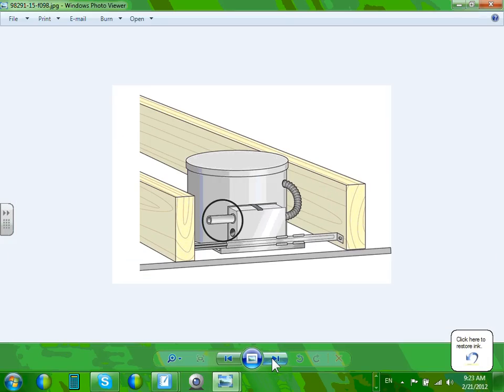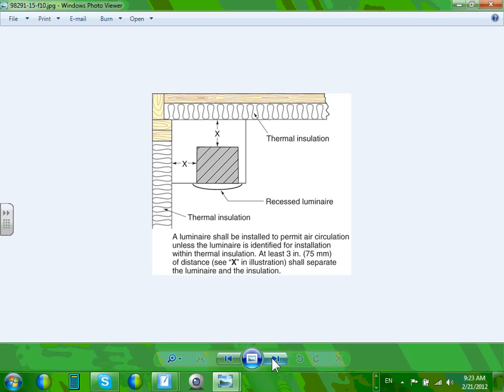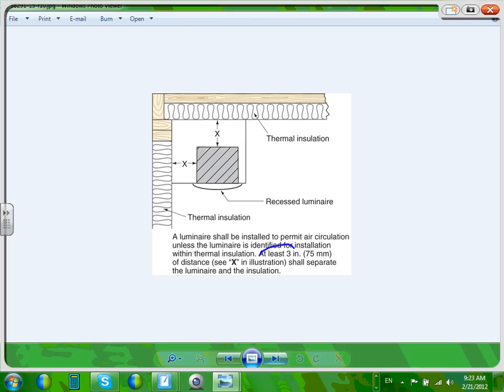When we talked about residential, guys, if your fixture is to be buried by insulation, which is not commonly used in commercial but in residential all the time, then your fixture has to be rated for what? IC, insulation contact, right? Everybody knows that from last year, IC. Otherwise, if you don't want to insulate them, then you have to separate them from thermal insulation with 3 inches, I believe. 3-inch separation, and who's going to go move the insulation? So most of these are insulation-covered, IC-rated fixtures.